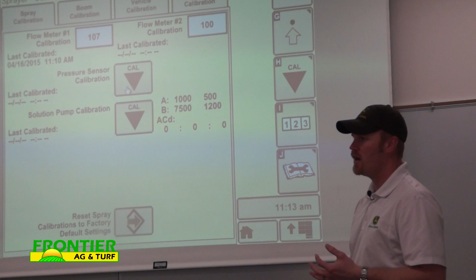Once you meet those requirements, you have water in the tank, you have the hydraulic oil temp to 140 degrees, then you can go through the calibration. It'll step you through it, you click the cal button, it's going to turn the pump on, it'll give you an amp reading at 3 psi, and it'll give you an amp reading at 150 psi, and that psi is based on your solution pressure sensor. So if that's off, your solution pump cal can be off. Okay?